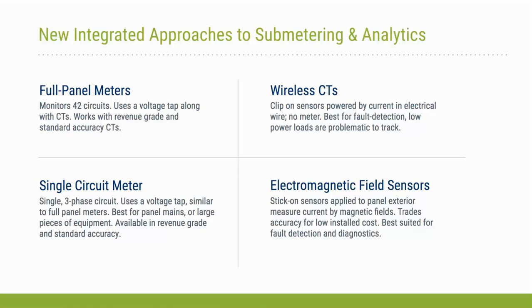The last one, which tends to be more recent and still in development, is what we describe as electromagnetic field sensors. These are stick-on sensors that go on the outside of the panel. There's no electrician required for this, and they are very easy to install. However, they come at the price of accuracy — as they only measure electromagnetic fields, there's a lot of interference between different breakers. So accuracy is not guaranteed by any means, though I'd say they are best suited for diagnostics and fault detection.